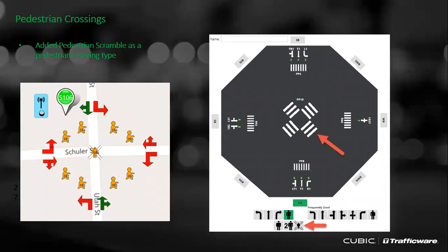To get the PED report working, do we need to make any modifications in the controller? You would need to enable these alarms. If alarm number 35 is not enabled in the controller, ATMS unfortunately will not see that and will not be able to generate the report. So that would be a prerequisite.